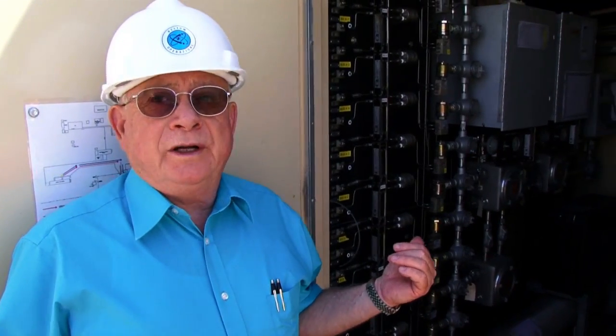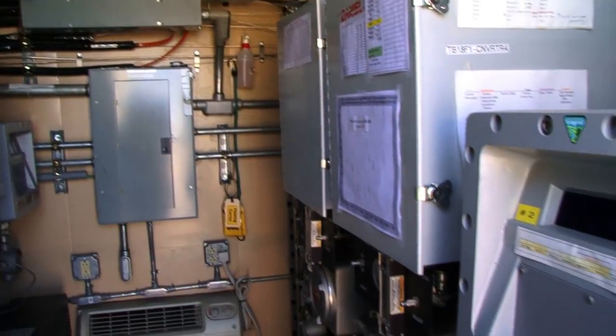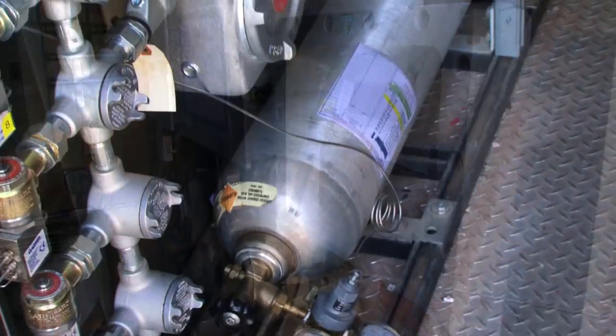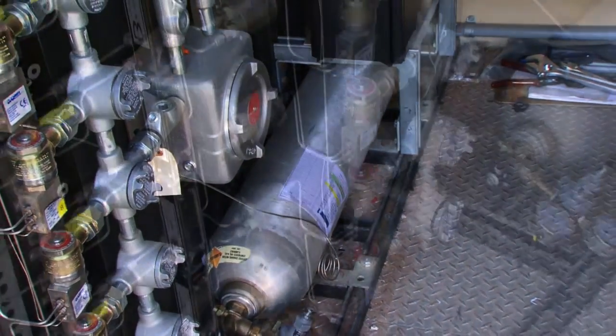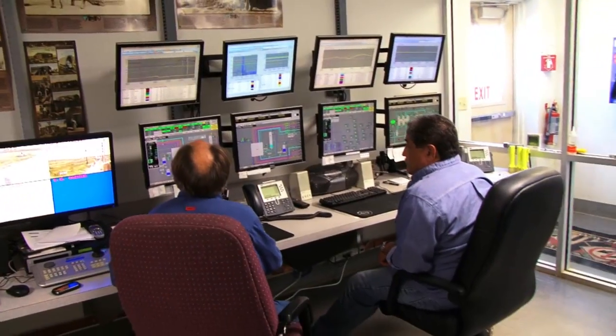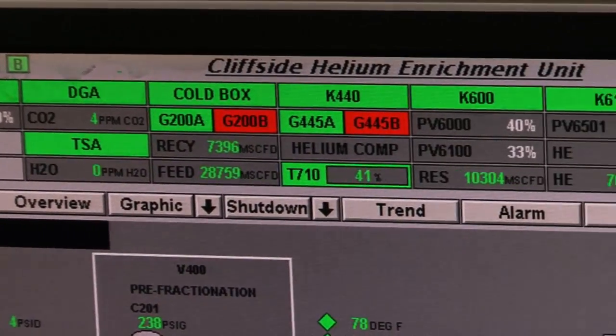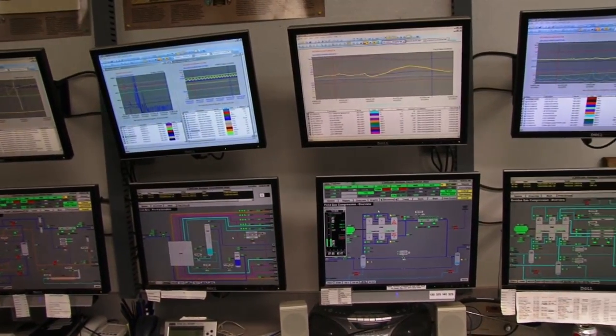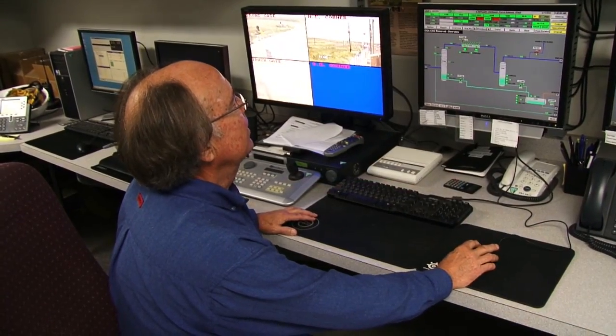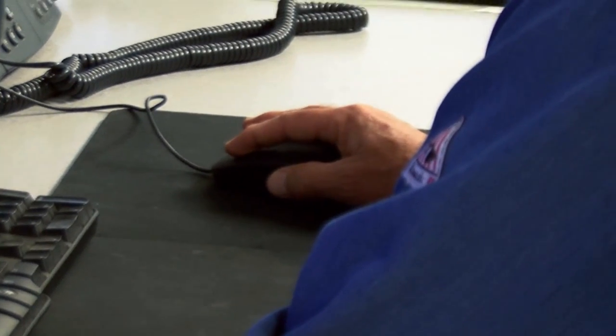This is the gas analyzer — one of the gas analyzers — that analyzes the gas coming from the field. It takes 20 minutes for each well to analyze, and the data is sent to the control room where operators see live gas analysis all the time. We are right now in the operating room of the helium operation. This control room monitors 23 wells coming into the plant. We process approximately 24-25 million cubic feet of total gas at 28% concentrated helium and push it in the pipeline at about 70-78% helium.